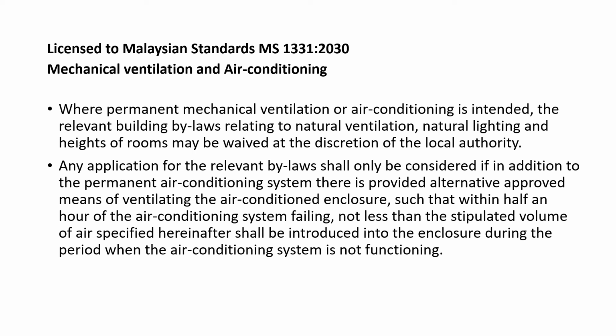So, according to Malaysian Standard MS 1331:2030, mechanical ventilation and air conditioning stated that where permanent mechanical ventilation or air conditioning is intended, the relevant building bylaws relating to natural ventilation, natural lighting and height of room may be waived at the discretion of the local authority. Any application for the relevant bylaws shall only be considered if, in addition to the permanent air conditioning system, there is provided alternative approved means of ventilating the air conditioned enclosure, such that within half an hour of the air conditioning system failing, not less than the stipulated volume of air specified hereinafter shall be introduced into the enclosure during the period when the air conditioning system is not functioning.